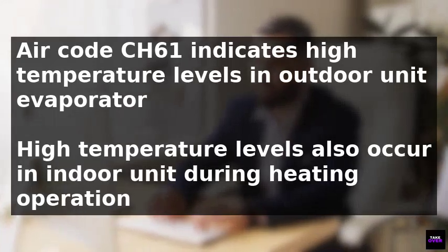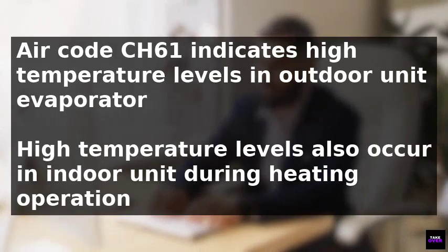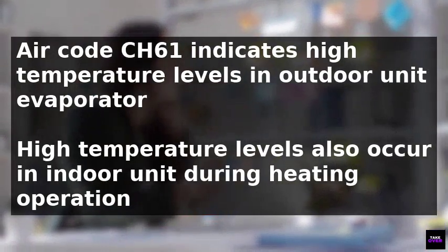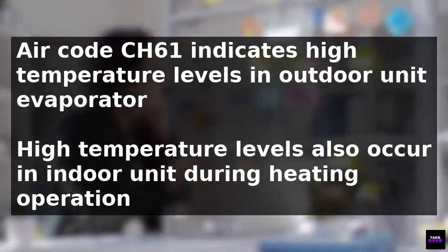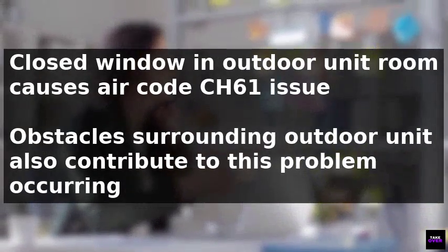The air code CH61 on an LG air conditioner indicates high temperature levels, either in the outdoor unit evaporator during cooling or inside the indoor unit during heating. This issue can be caused by a closed window in the outdoor unit room, obstacles surrounding the outdoor unit, or a clogged indoor unit filter.